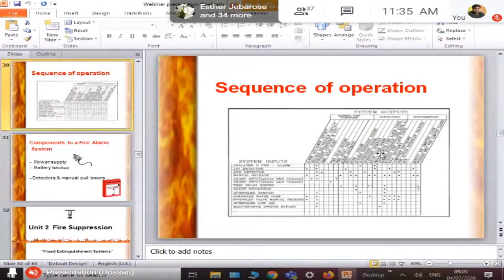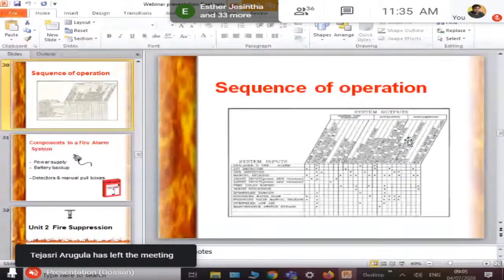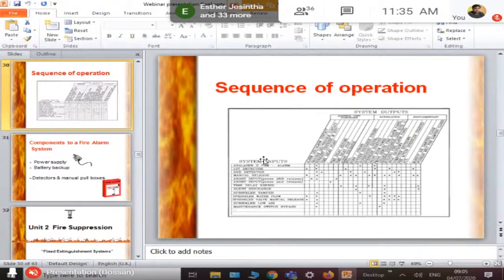This is how the sequence of operation looks like. So what is a sequence of operation? If you see in the left side tab, you have system inputs. These are the input devices. So you'll have the detectors listed out here, and whatever input devices you have, you will be listing out here based on zone and zone separations. Okay, it might be floor, it might be zone, it might be area, whatever. And you will have all the output devices here. So you will have the lift, the access control systems, the pumps, the generators, and all those things, and the notification devices, very important. The notification devices will be in here.